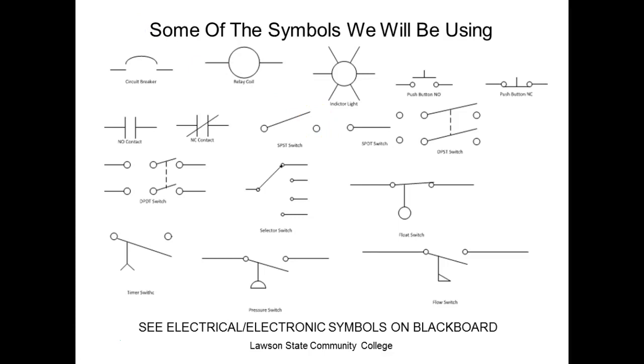These are relay contacts - switches that are controlled by the relay. So when we passed that relay around, you noticed it had switches on top of it; we call those switches contacts. We can talk about those. We have different sensors, like float switches - does anybody not understand what a float switch is?